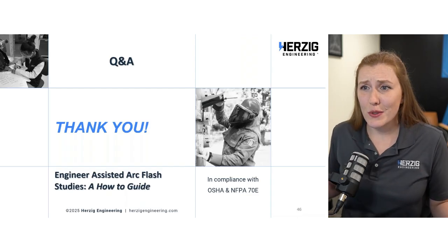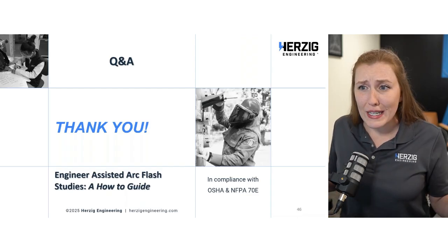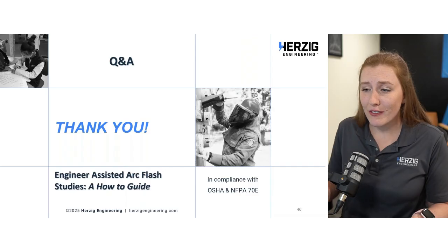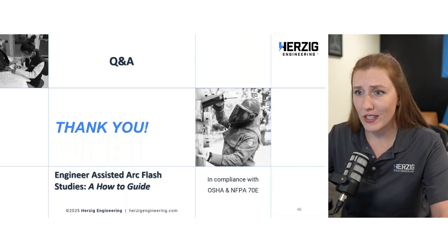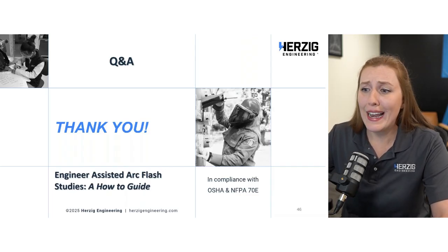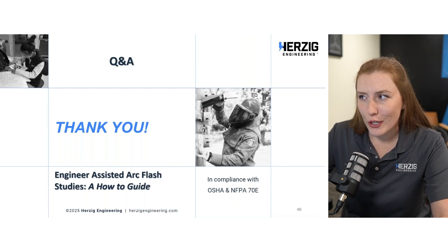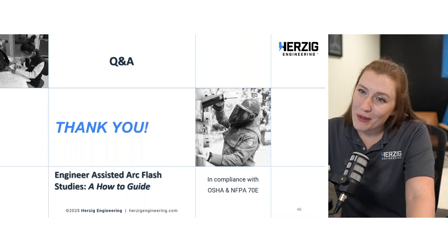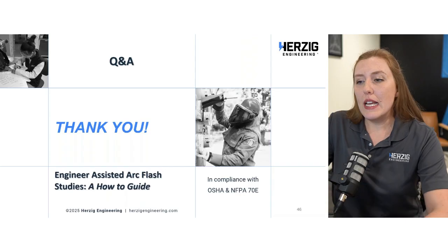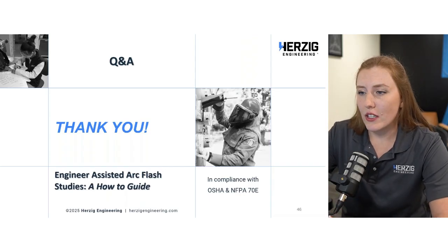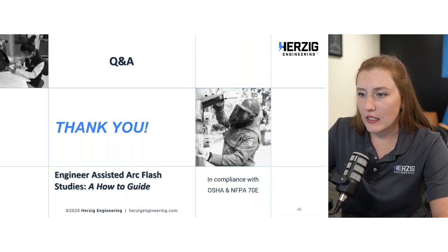Put those insulated tools away, except for worst case scenario or as a backup, but stop servicing, adjusting, and replacing stuff while it's energized. 99.999% of the time, you can turn it off. You just don't want to jump through the hoops to do it. But it's definitely a priority to turn it off. So you definitely still need to have the study to make sure that you're safe during that process.